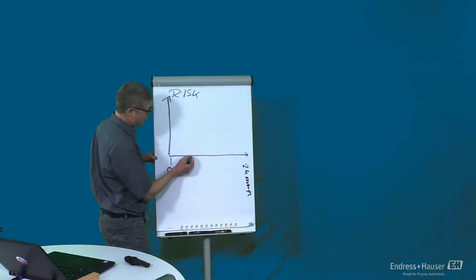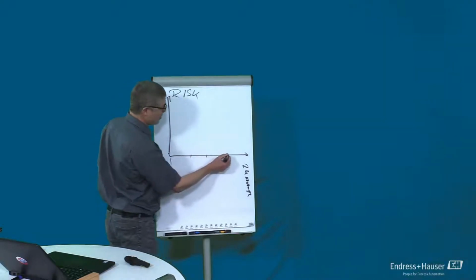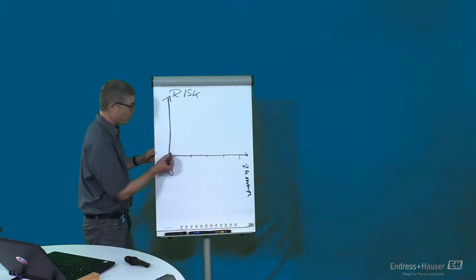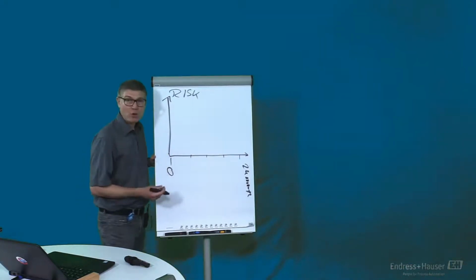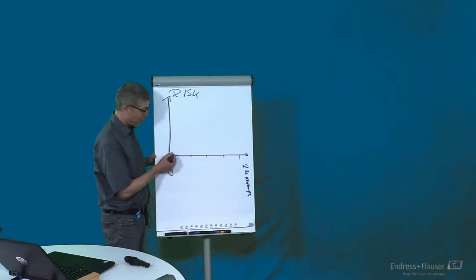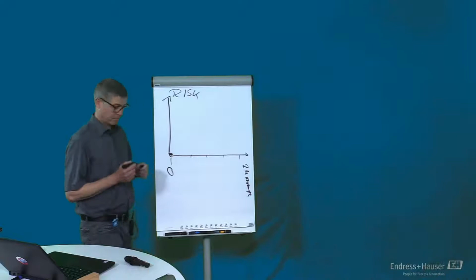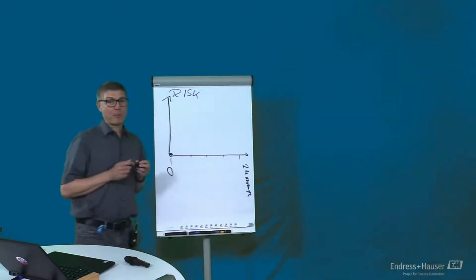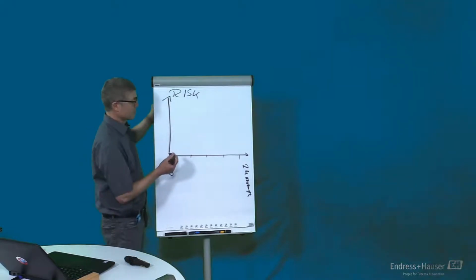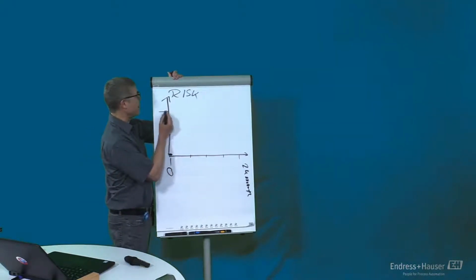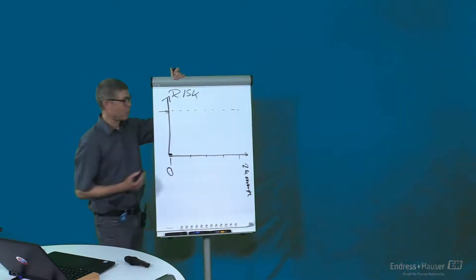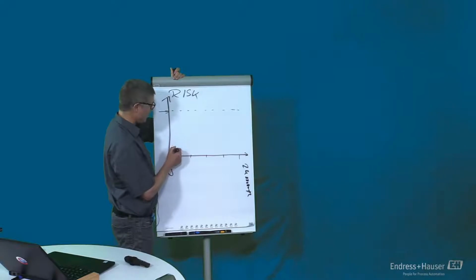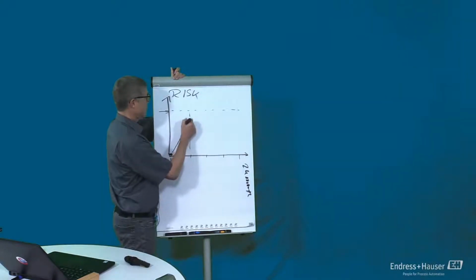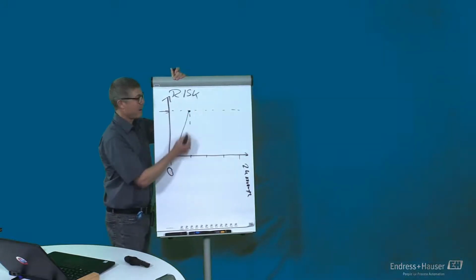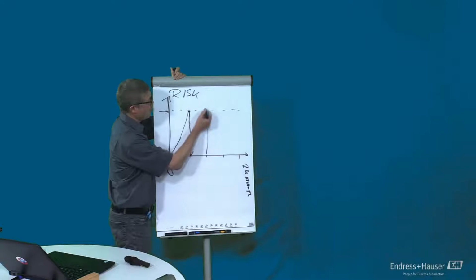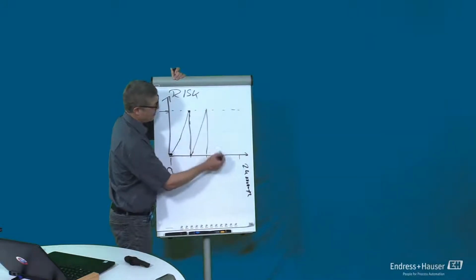You do your calibration, the majority, in 6-month intervals. So you do your calibration, your sensor is good according to your procedures, and you say, yeah, then my risk is 0. So you do the next calibration 6 months later. You do this because you have set a limit for the acceptable risk. And you think, if I do this calibration every 6 months, my risk is limited, and then you do the next calibration, and you come to a graph like this.